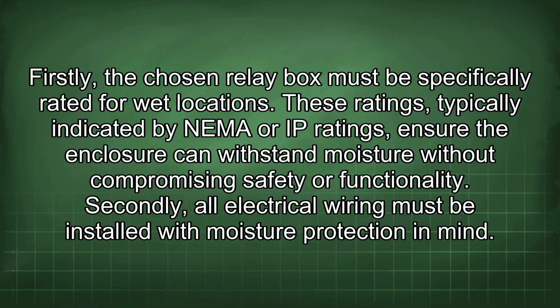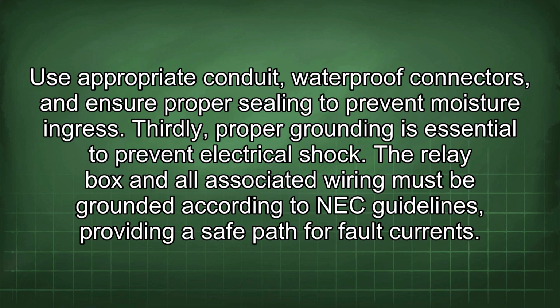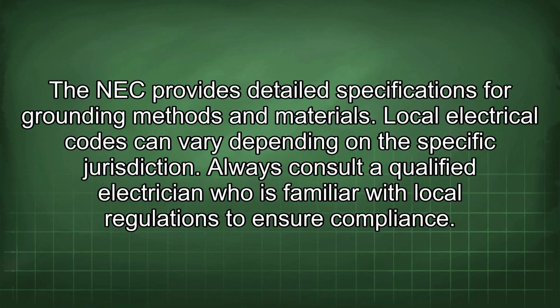Secondly, all electrical wiring must be installed with moisture protection in mind. Use appropriate conduit, waterproof connectors, and ensure proper sealing to prevent moisture ingress. Thirdly, proper grounding is essential to prevent electrical shock. The relay box and all associated wiring must be grounded according to NEC guidelines, providing a safe path for fault currents. The NEC provides detailed specifications for grounding methods and materials.